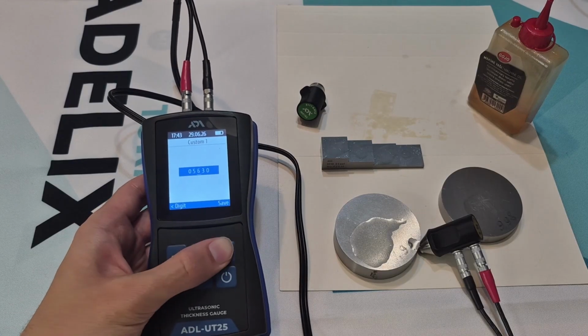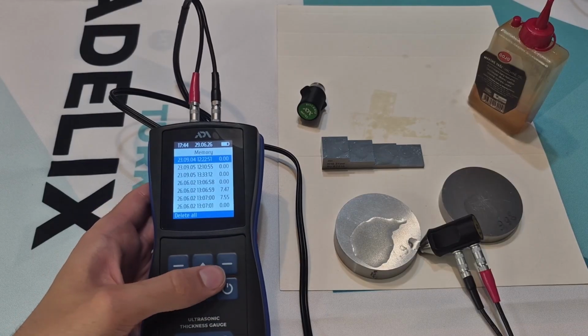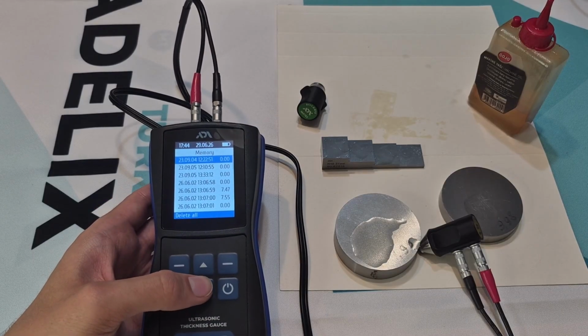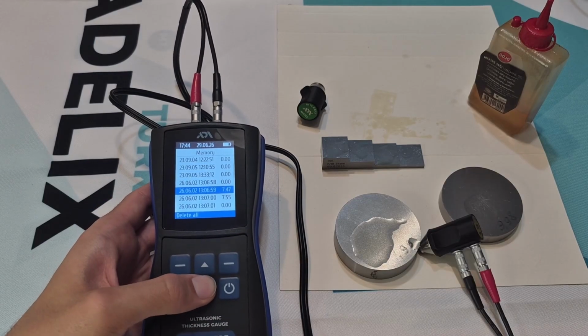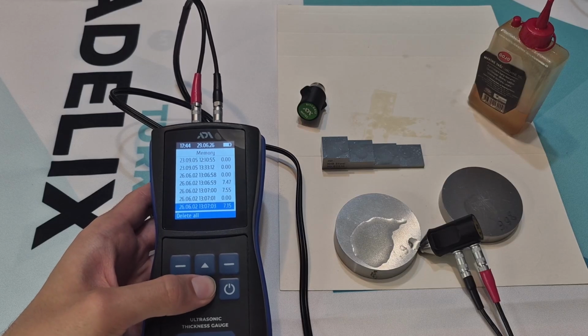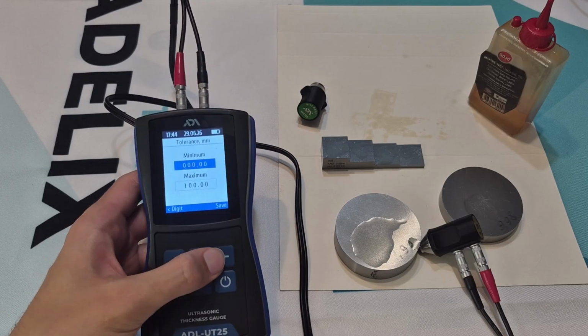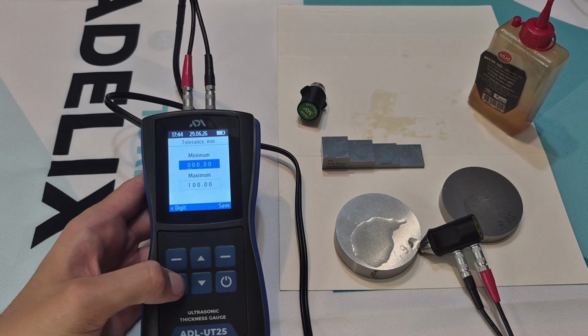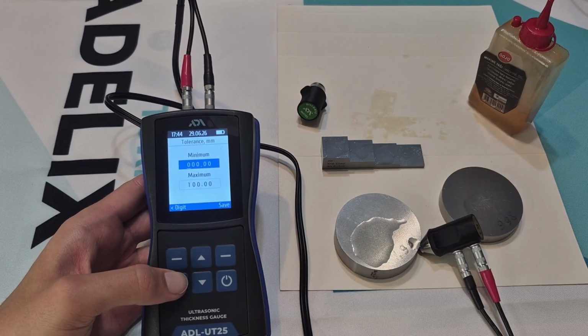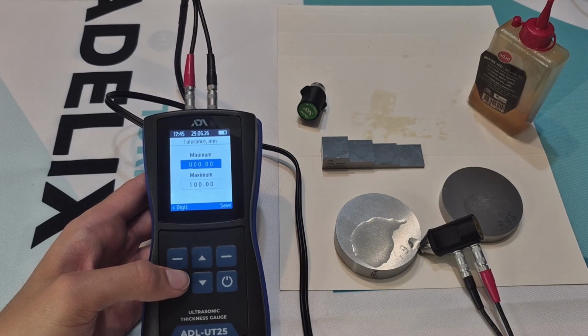The next section is Memory. All completed measurements are stored here. A separate B-scan memory section is used to store results obtained in B-scan mode. The next item is Tolerance. Here the minimum and maximum allowable thickness values are set. If the measurement result goes beyond the set limits, the device will automatically warn the user.